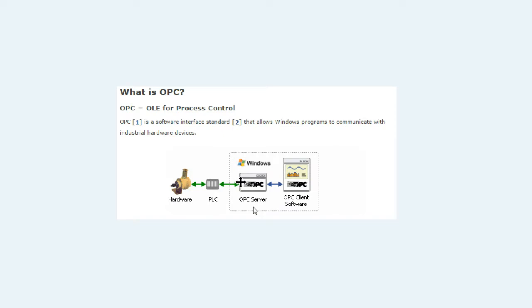The server can serve data to any number of OPC clients that read the data from the server. Typically, the client software resides on the same PC as the server software — it doesn't have to be, but that's generally how it's done. StripChart OPC is basically client software, and it relies on a server installed on the user's computer to access the data in the PLC.